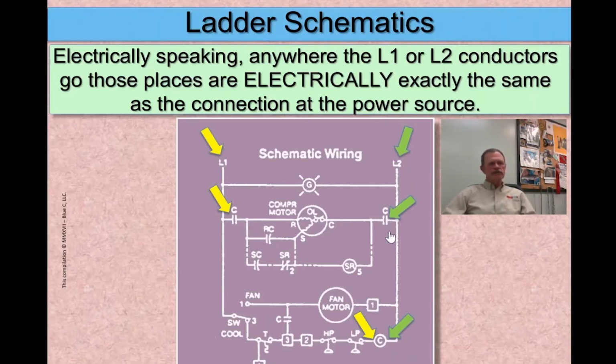For example, here in the CC, the compressor contactor, here's a schematic of a very simple air conditioning unit, probably something you guys have worked on a lot. When I energize L1, turn on the switch, throw the disconnect, trip the breaker, L1 is hot everywhere through this circuit, in this case up to one side of the contactor switch. The contactor switch is open, so it's not hot there or beyond it.